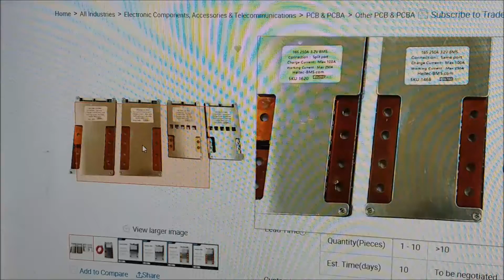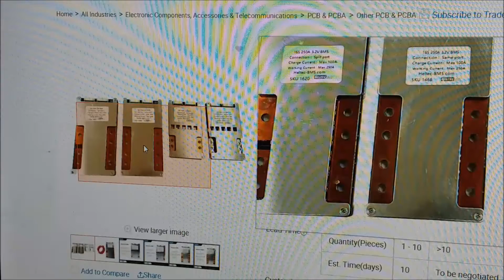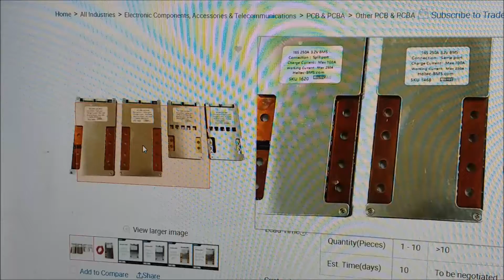Two adjacent cells can transfer a really small current, like 0.6 of an amp. But it can't transfer from the highest cell in the pack to one that's 8 cells away - it has to load-share bits and pieces, one to the next, one to the next. It takes forever. Once you get it balanced, it pretty much stays that way. But initially, even if you charge them all the same before putting the bus bars across, that's called top balancing, and that'll work.